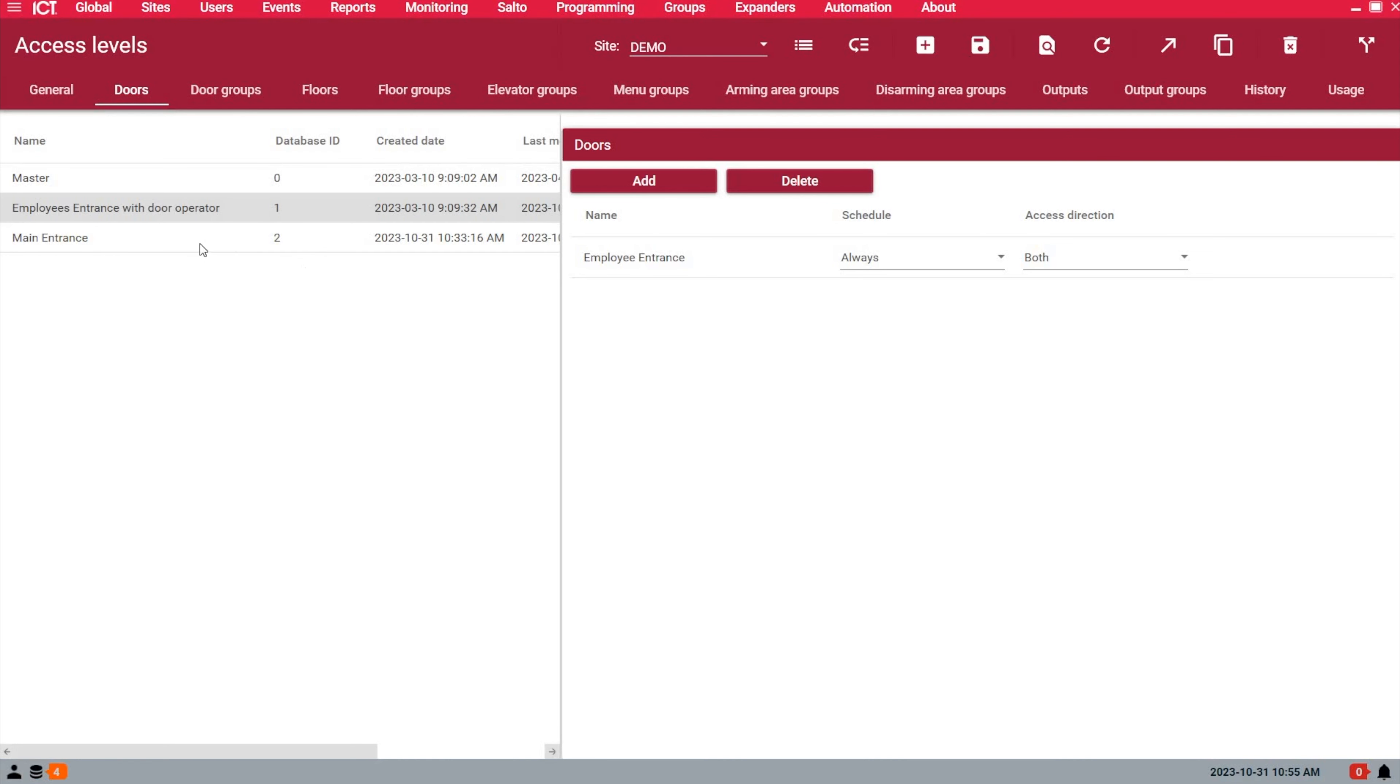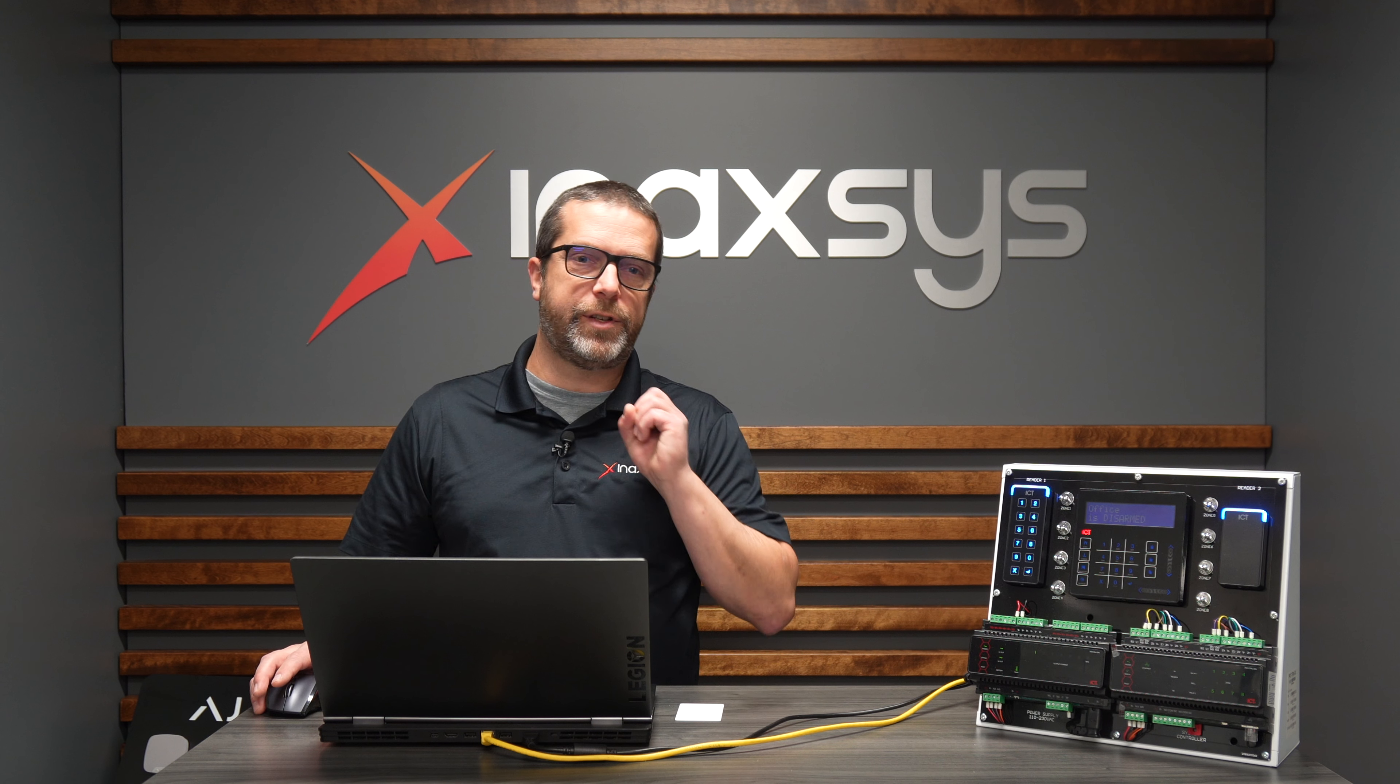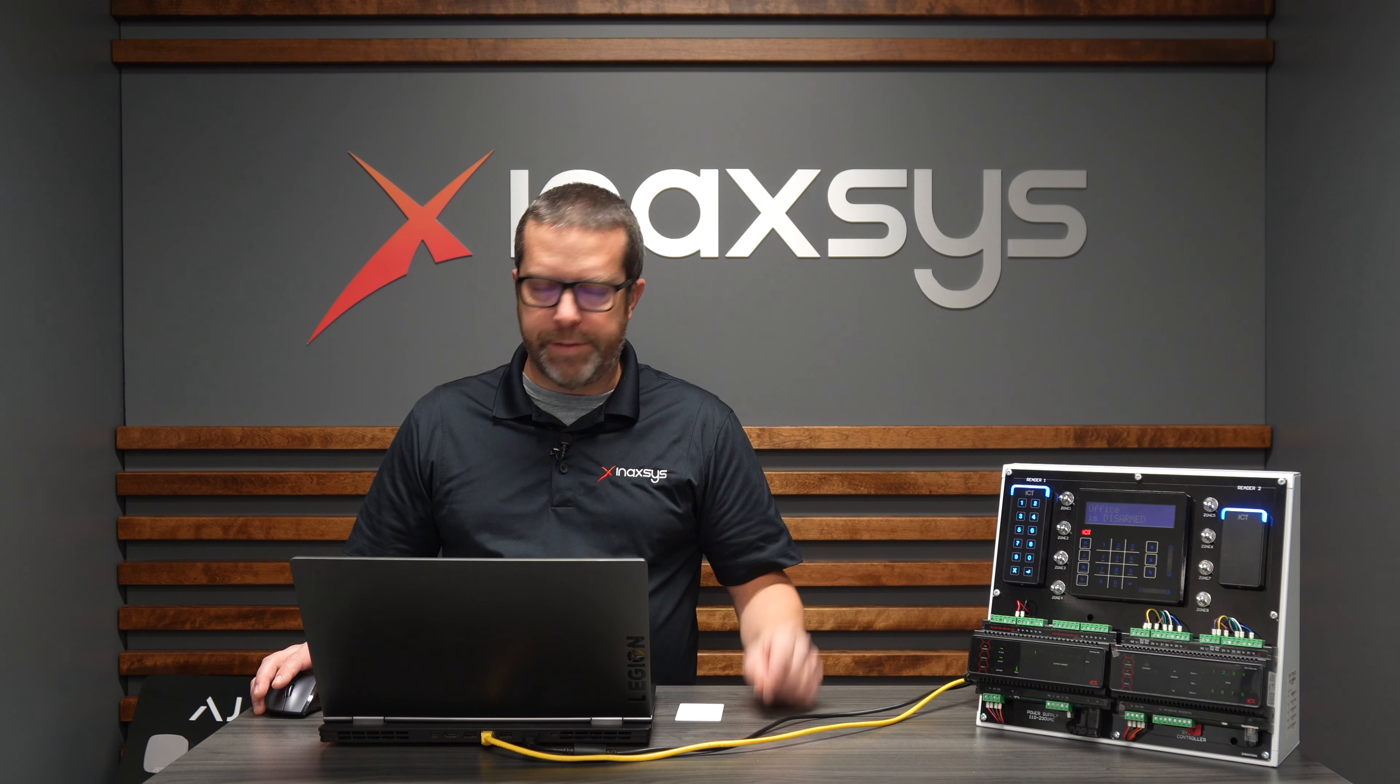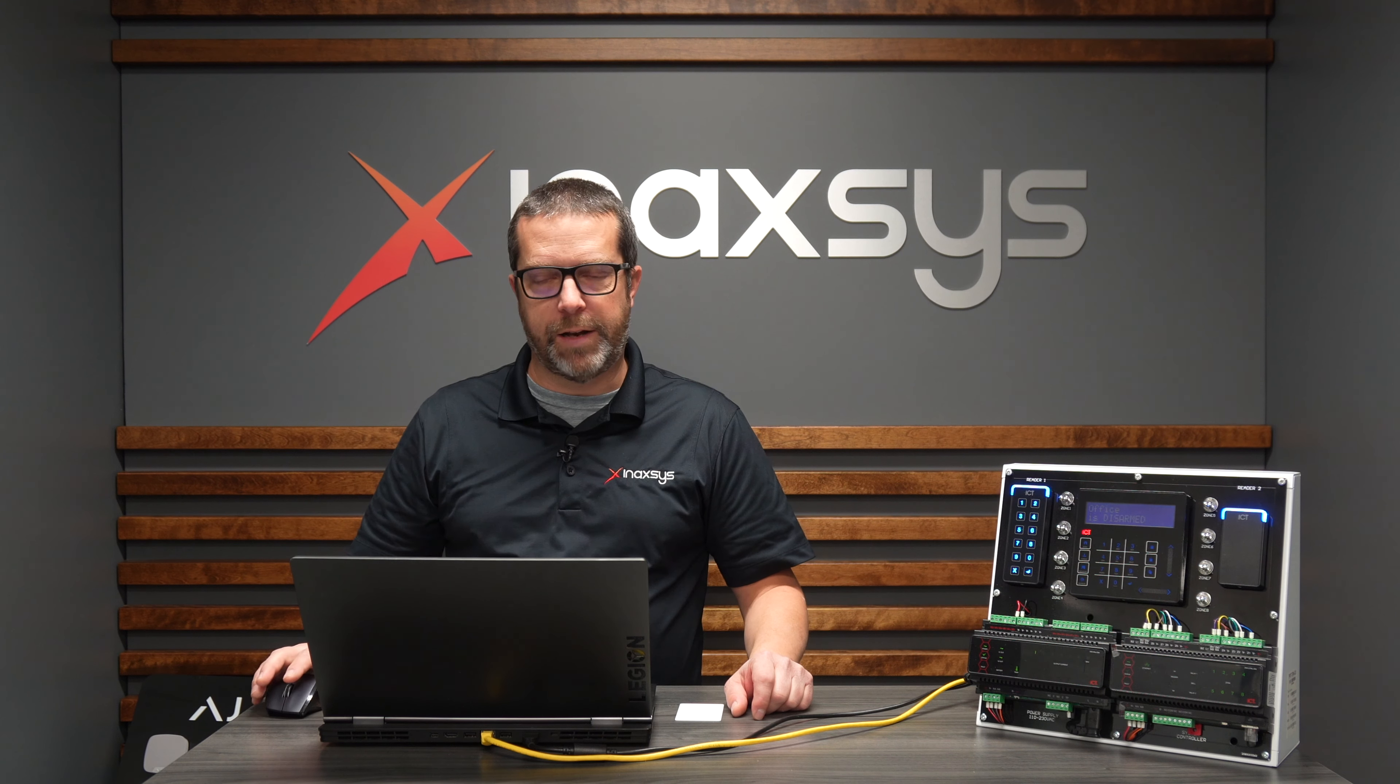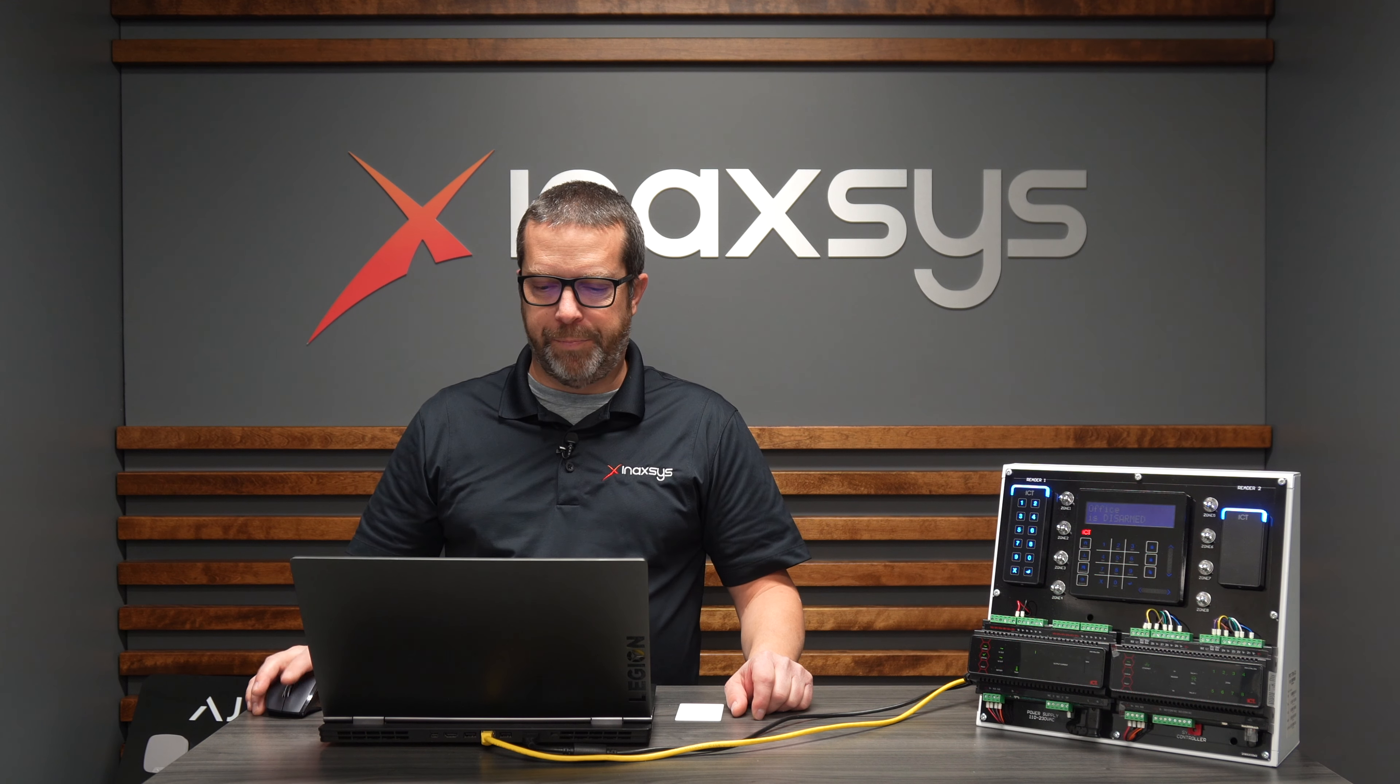Under this access level, under the General tab, you have 'reader access activates output.' I decided to use three seconds for the activation time. If you're just giving a pulse to a door operator, one second might be enough. I used three seconds so we can see the status change in my status list when we test it.